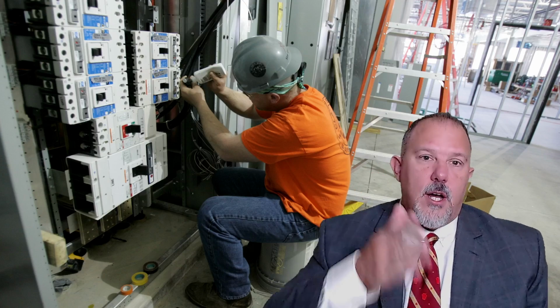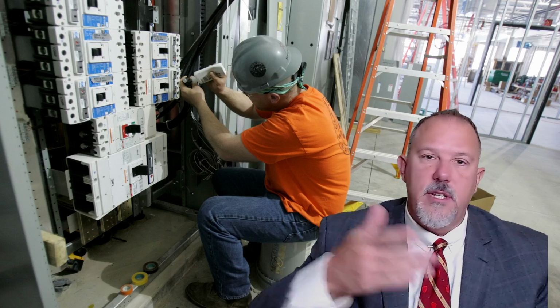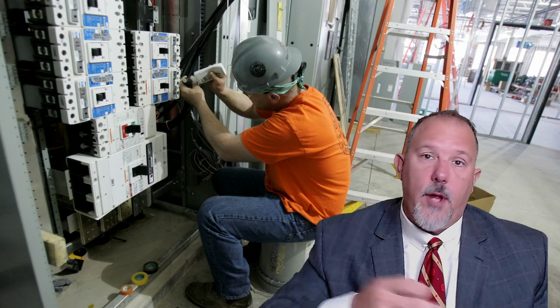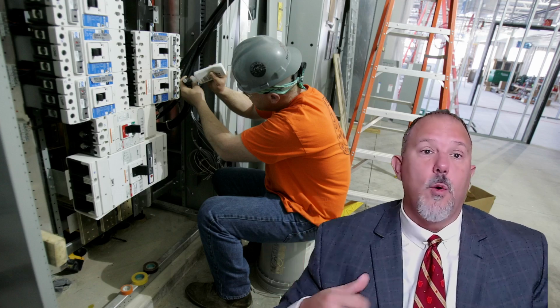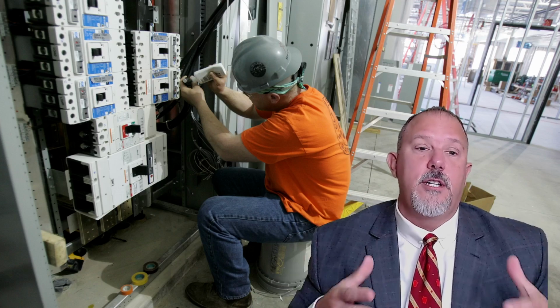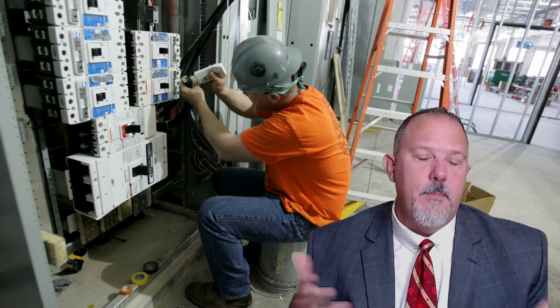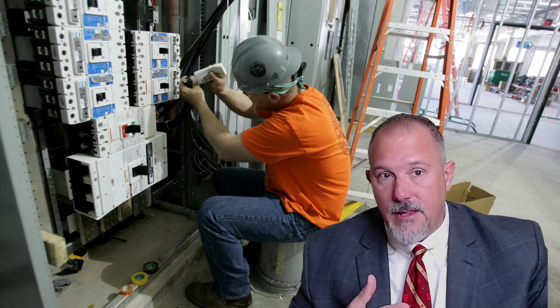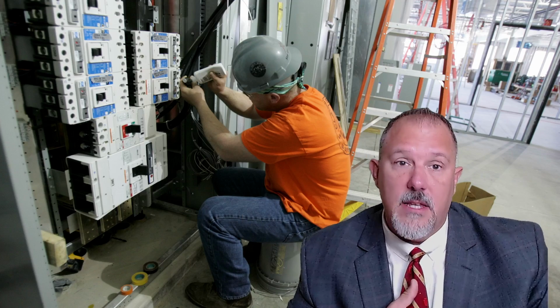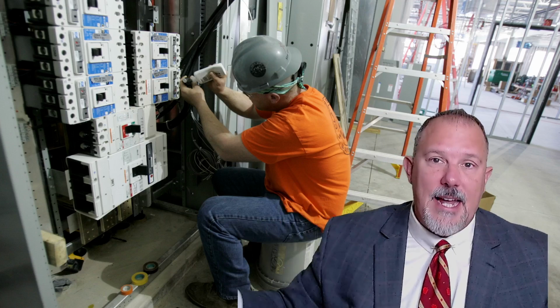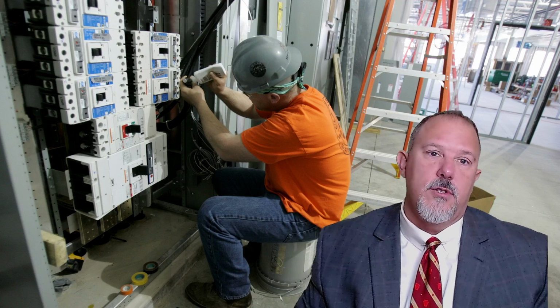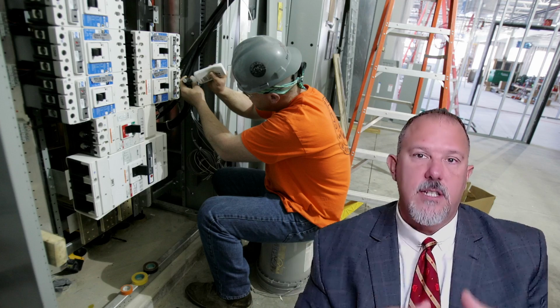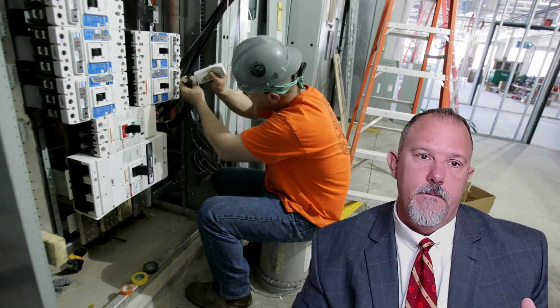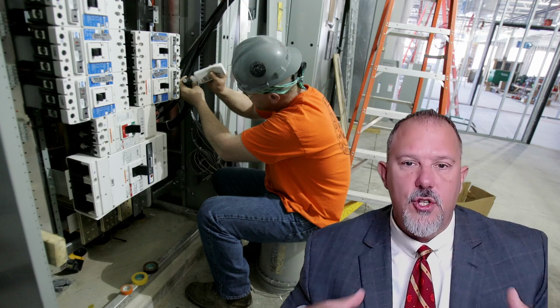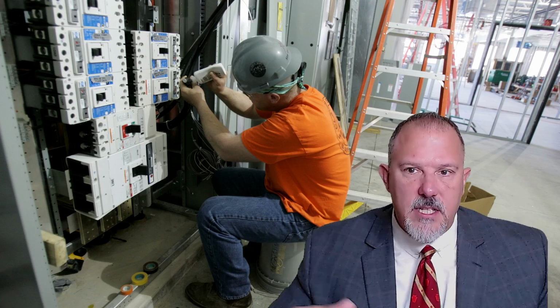Now, we can talk about establishing an electrically safe work condition and what you should be doing. This gentleman here is working in an electrically safe work condition. Why? Well, it's a brand new facility, but in any case, there's nothing supplying this. But if there was something supplying this equipment, it would be locked and tagged out. They would have gone through all the procedures and established an electrically safe work condition so they can get their work done. But my point in here is you want space in front of equipment.